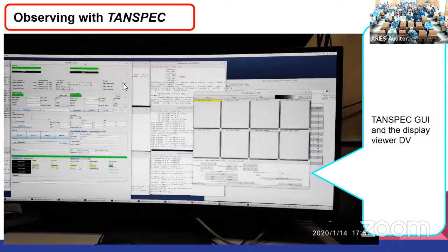And also here, you select that in the spectrograph, or the H2RG array, there are 2 gain modes, the high gain and the low gain mode. You can just click here, and by default it always remains in the high gain. You can click to toggle between high gain and low gain, so based on your criteria you can change it.